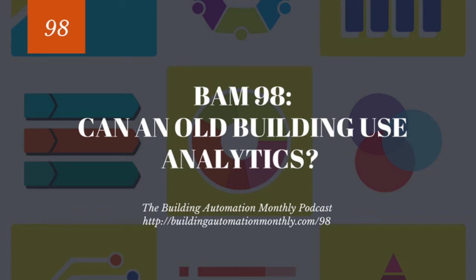Will we be? Yes. And I think it goes back to this earlier thought that we had on the lack of trained resources that some of these facilities are going to have. We are actually piloting something like this right now with a number of clients. Fairly simple: the ability to manage set points across broad, disparate campuses, time schedules, very simple things, hydronic loop optimization. So going back to your talk about mapping the preheat valves earlier, we've got the ability to actually monitor the valve positions and change the loop pressures, which in turn optimizes the central plant delta T's.